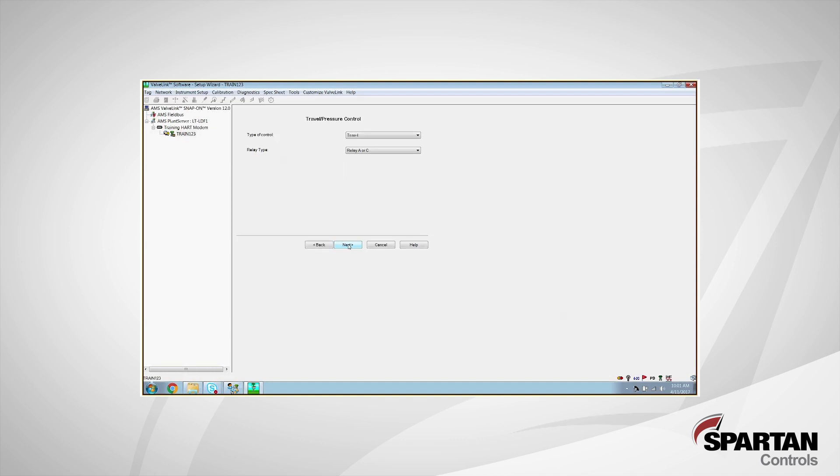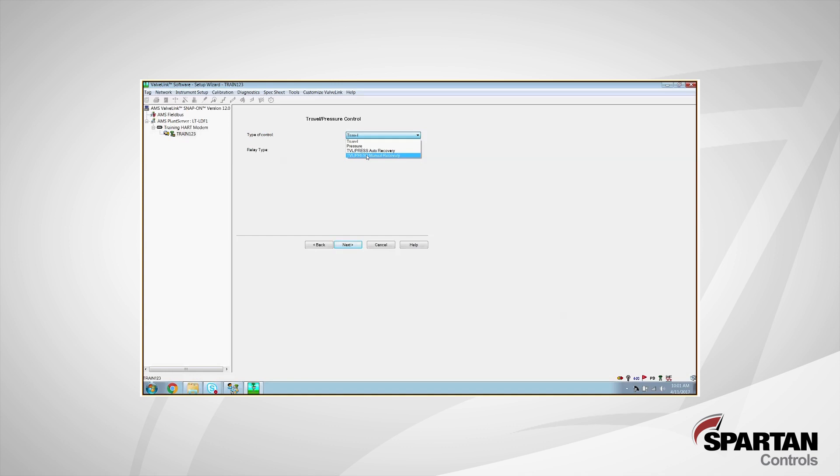What type of control do we want? Generally speaking, our customers use travel control, but if you have an AD and above diagnostic level, you will be given the option to have pressure recovery modes as well. And what this means is that on loss of signal from our travel sensor, it'll actually go into a smart pressure control mode where it acts like a smart I2P. There are two options under this heading. There's either auto recovery or manual recovery. When our customers do choose to use this option, we always recommend using the manual recovery mode, which means that on loss of travel sensor, you have to repair it and then tell the DVC to go back into travel control mode before it'll go back to it itself. Otherwise, it'll automatically just go back into travel control mode if you have it on auto, which could lead to problems, especially if you have dead spots in your potentiometer or if your magnetic array is misaligned but kind of giving you a signal. For us today, I'm just going to use travel control.